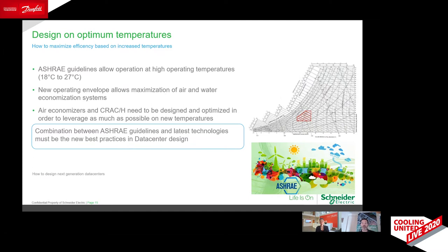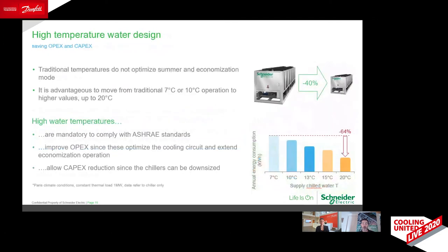So this requires a different technology for air conditioning units, for chillers, for all the devices that reject the heat. Certainly, if the air conditioning unit is designed to work at 25, 26 degrees Celsius, water temperature could be 20 degrees Celsius, much higher than in the past. So the chillers are not rated or designed at 7, 12, or at 10, 15 anymore. They are designed at 18 or 20 degrees Celsius.